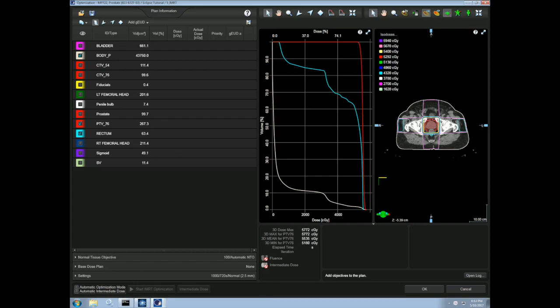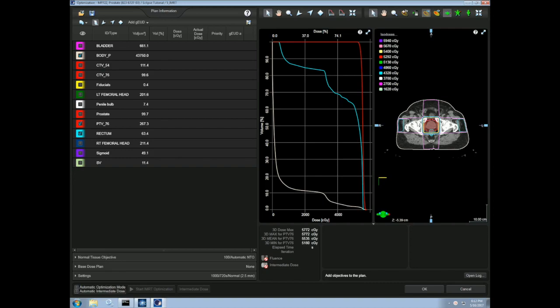It is important to note at this point what the difference between our optimized fluence map and our final dose distribution is. You may have noticed that I talk about fluence when we are discussing optimization and not dose. This is because our optimization algorithm is optimizing the fluence and not the actual MLC sequence. This is important because once our optimization is complete, we will have an optimized fluence map, which may be slightly different than our actual delivered fluence from the MLC sequence.